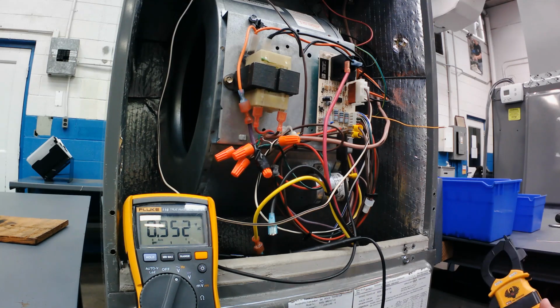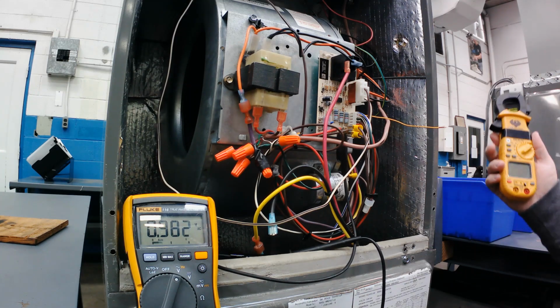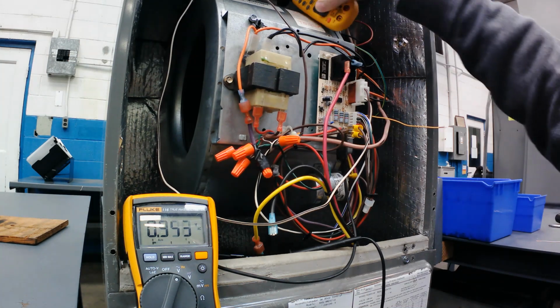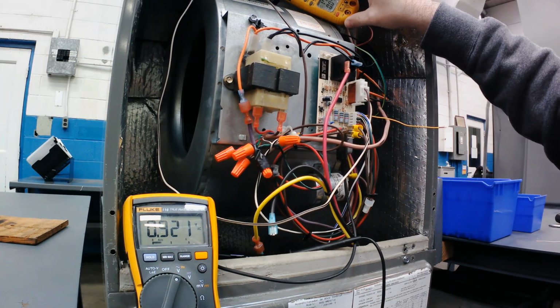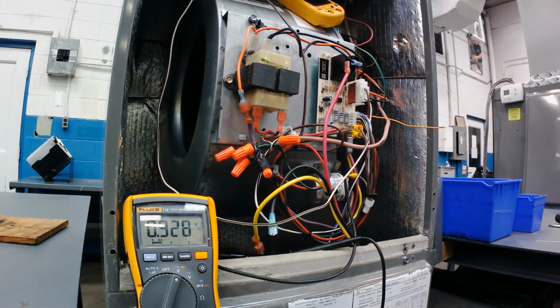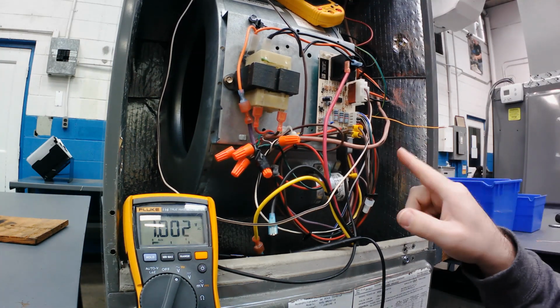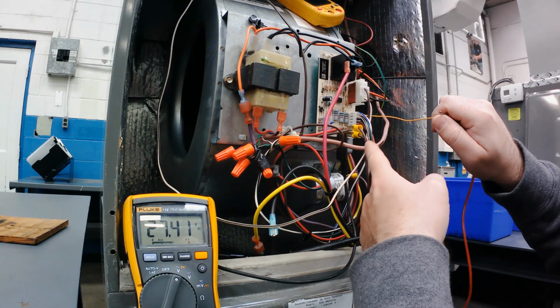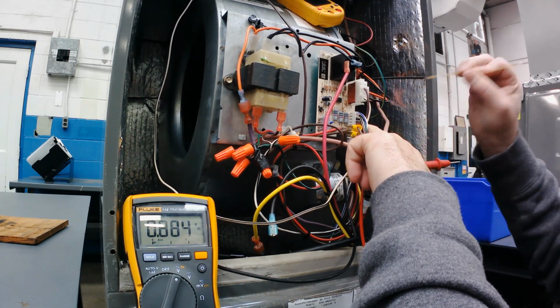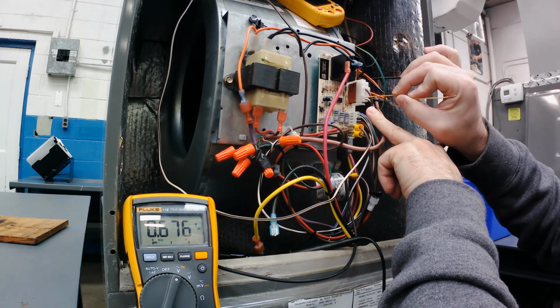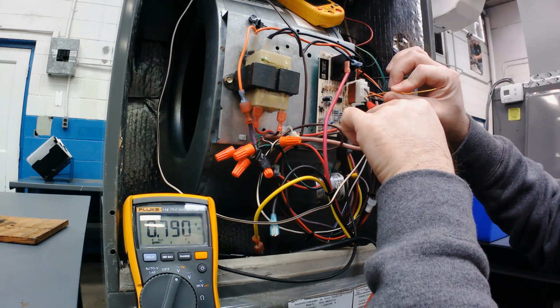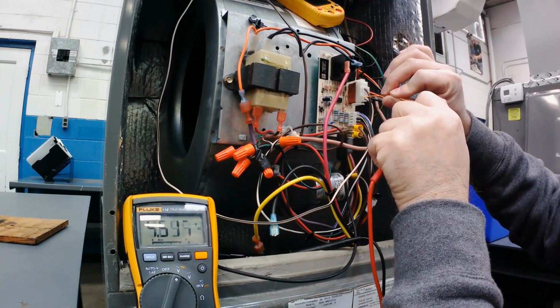We can check our amperage with our clamp meter here. So I've got 17 and a half amps or so on my electric heat, and I don't have a 24 volt call for G. So what's bringing it on? It's the W circuit. So one lead on the transformer common and the other one on the W1, and that proves power into my board. I could prove power out of my board. If you were not getting your heat sequencer to come on, you could easily put this thermostat wire inside that little plug, and I get 27 volts coming out of the board.